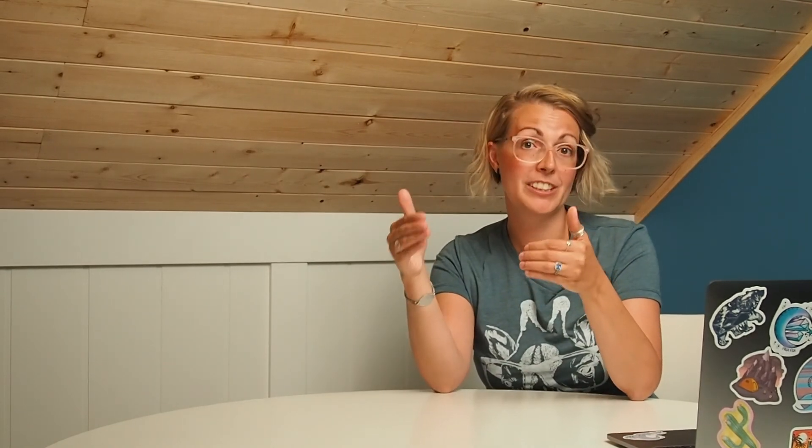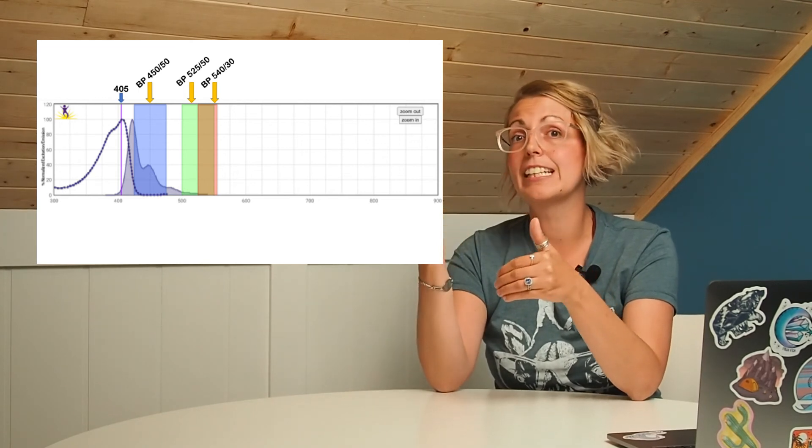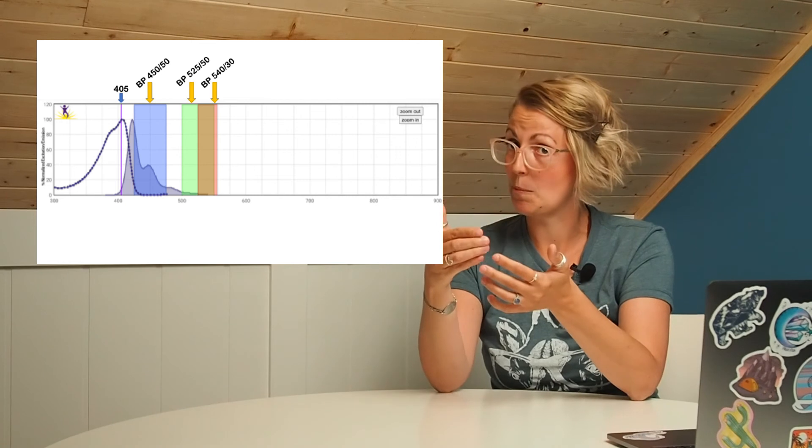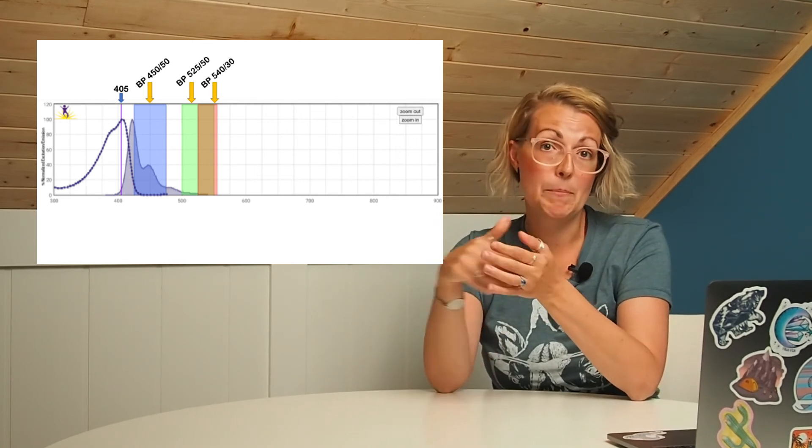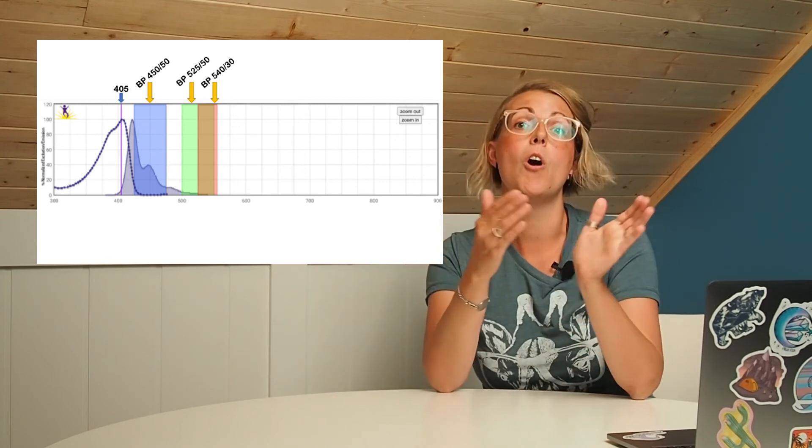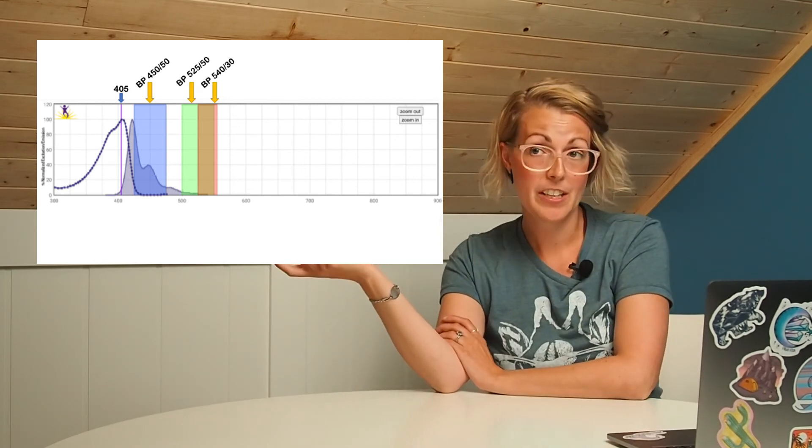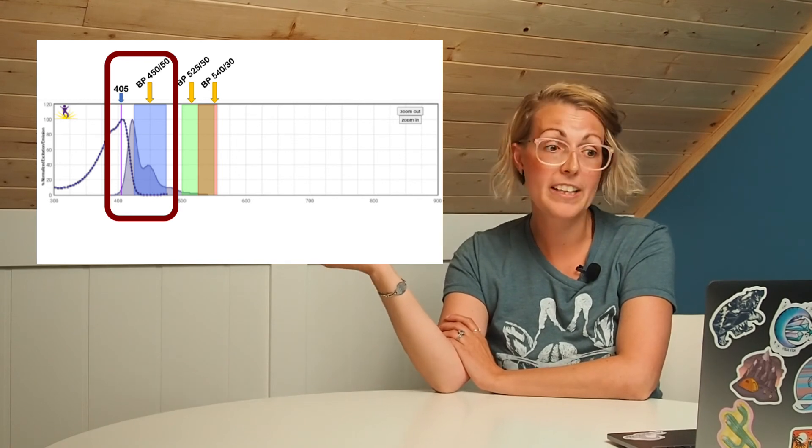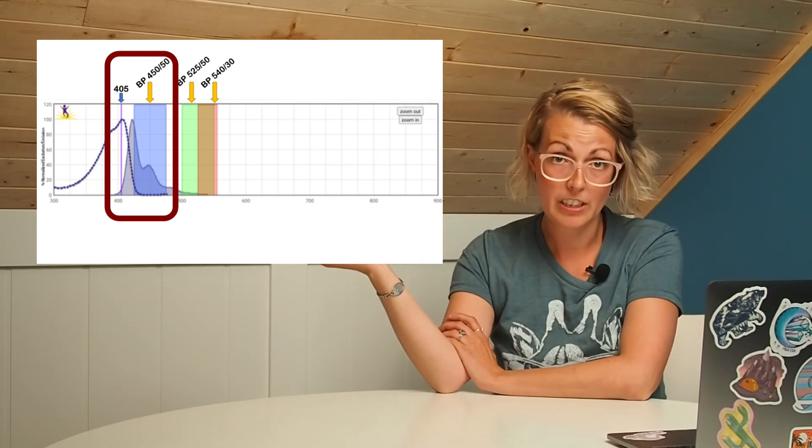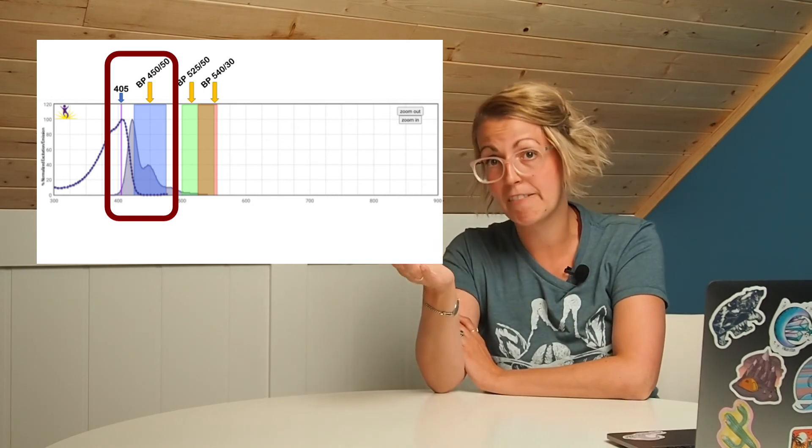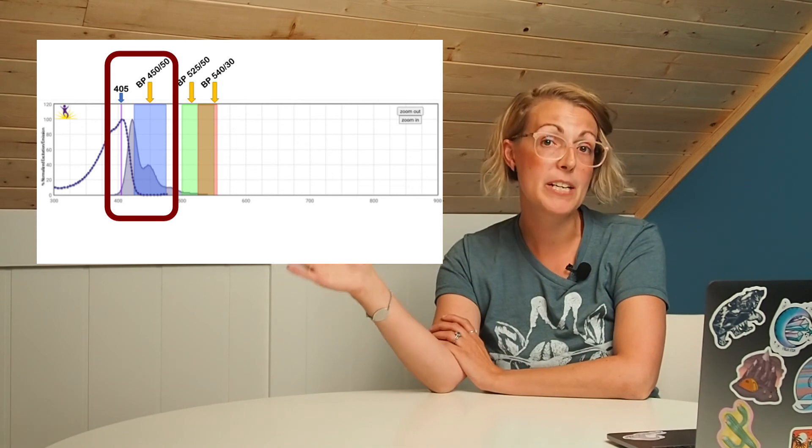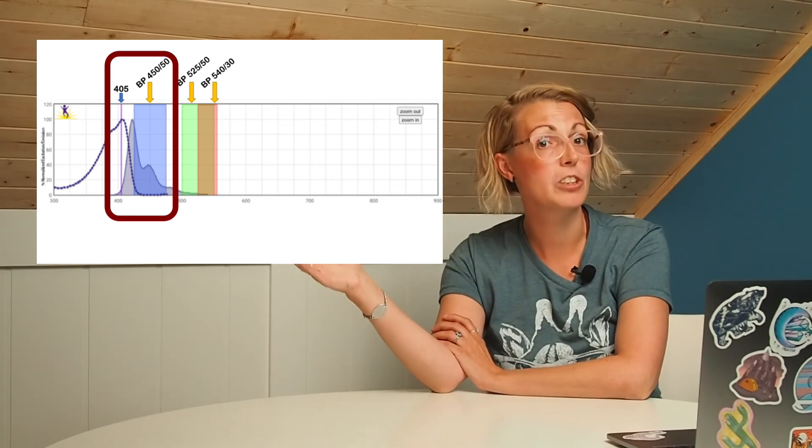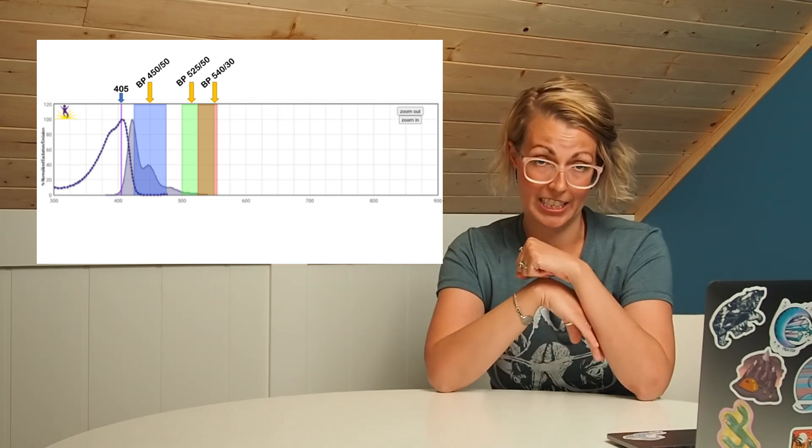Going back then to determining which fluorochromes we can use, after you determine if you have a laser to excite a fluorochrome you then need to determine if you have a filter set that will detect the emission. In order to do this you would then look at the emission profile from that fluorochrome and ideally you would want the peak of that emission to be falling within one of the filters that you have on your instrument. As you can see in the example here the peak emission falls within the 450 slash 50 filter, meaning that we will both be able to excite this fluorochrome with a 405 nanometer laser and detect the emission with a 450 slash 50 filter, meaning that this fluorochrome can be used on this machine.